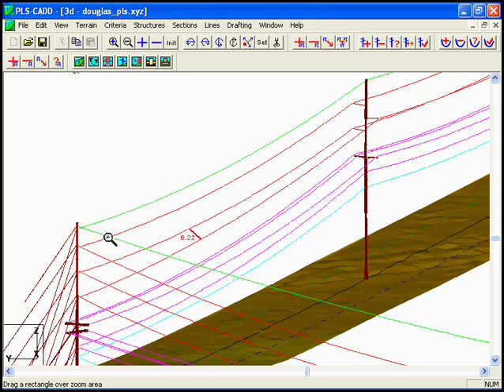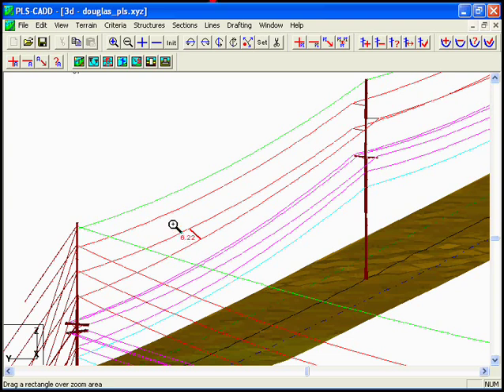So in this particular case we do have a violation. We need to do some modifications or switch the phases in order to eliminate the minimum eight foot requirement that we have between the 115 kV circuits.